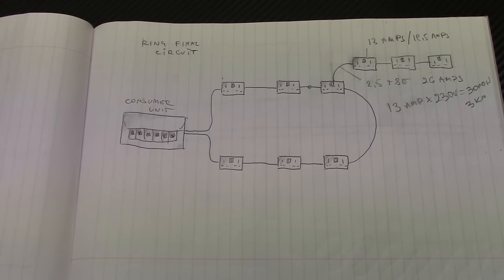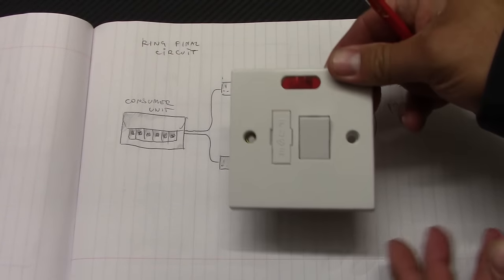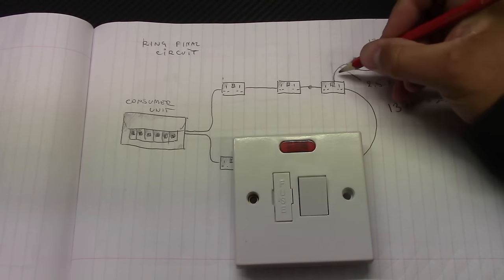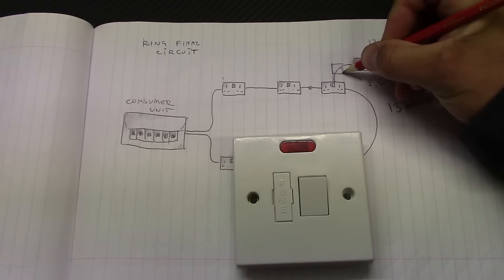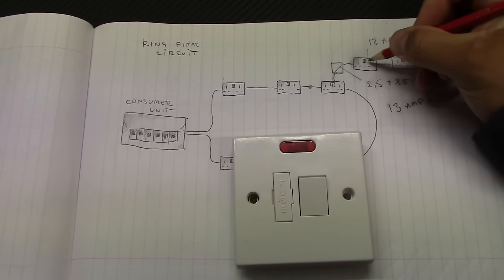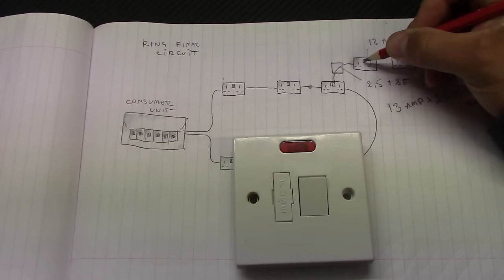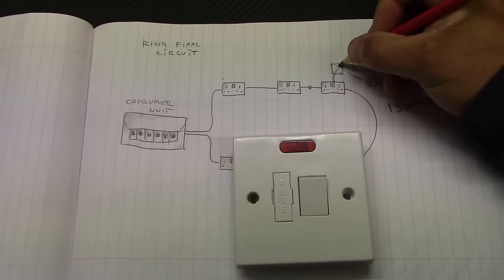So the right thing to do is to install FCU, fused connection unit, somewhere in here on this piece of cable before the first unfused spur. So now obviously this unfused spur and the rest becomes a fused spur because you've got the protector here.